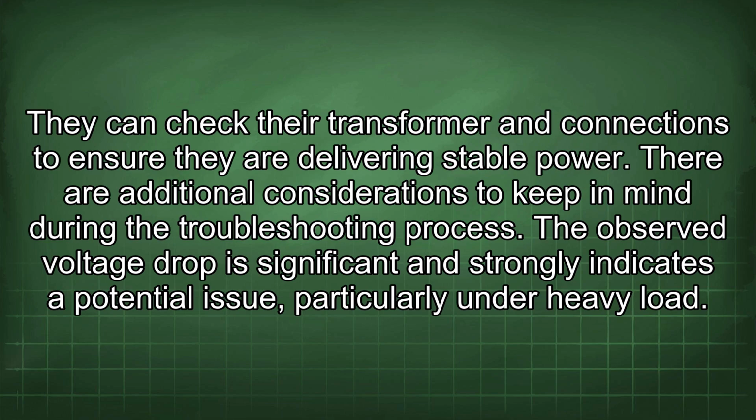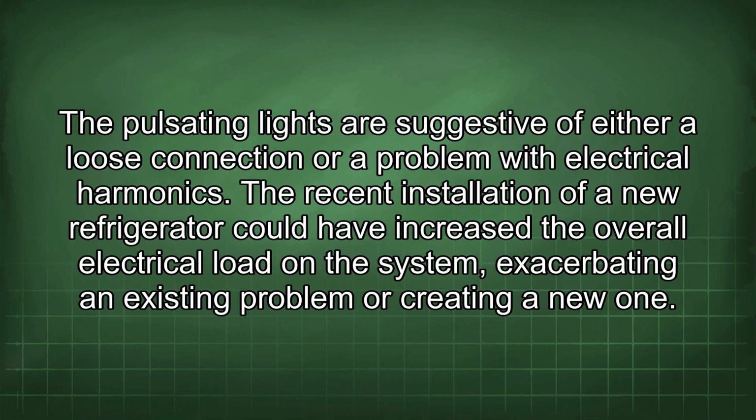There are additional considerations to keep in mind during the troubleshooting process. The observed voltage drop is significant and strongly indicates a potential issue, particularly under heavy load. The pulsating lights are suggestive of either a loose connection or a problem with electrical harmonics. The recent installation of a new refrigerator could have increased the overall electrical load in the system, exacerbating an existing problem or creating a new one.